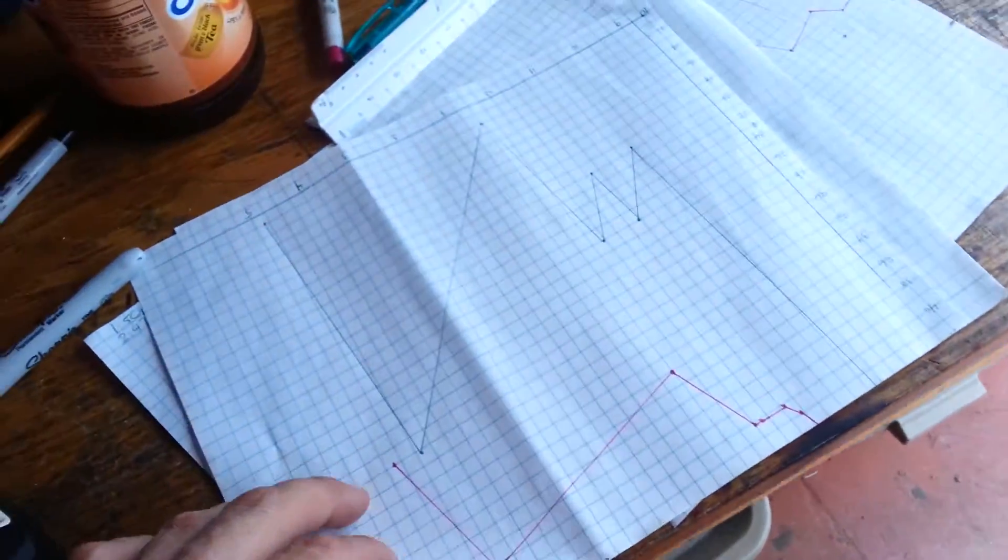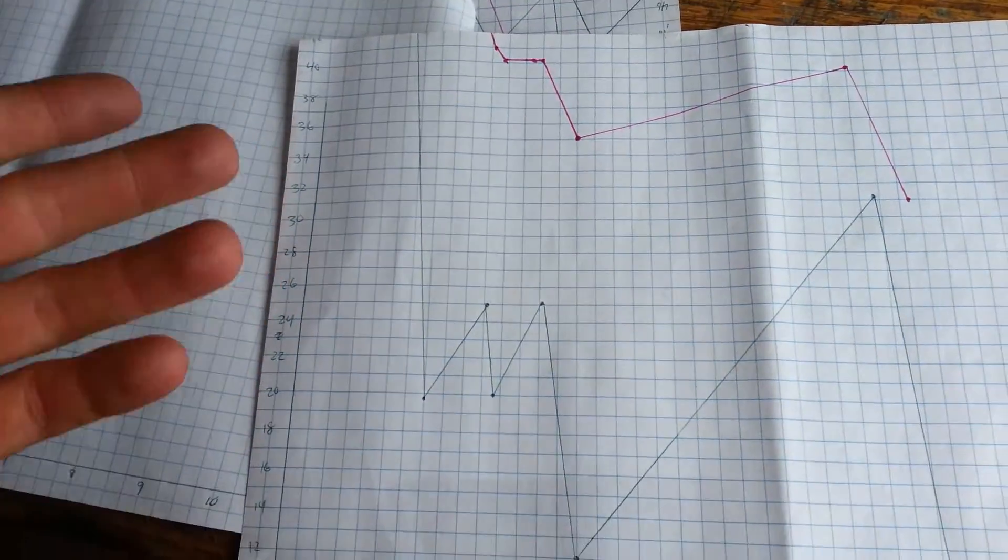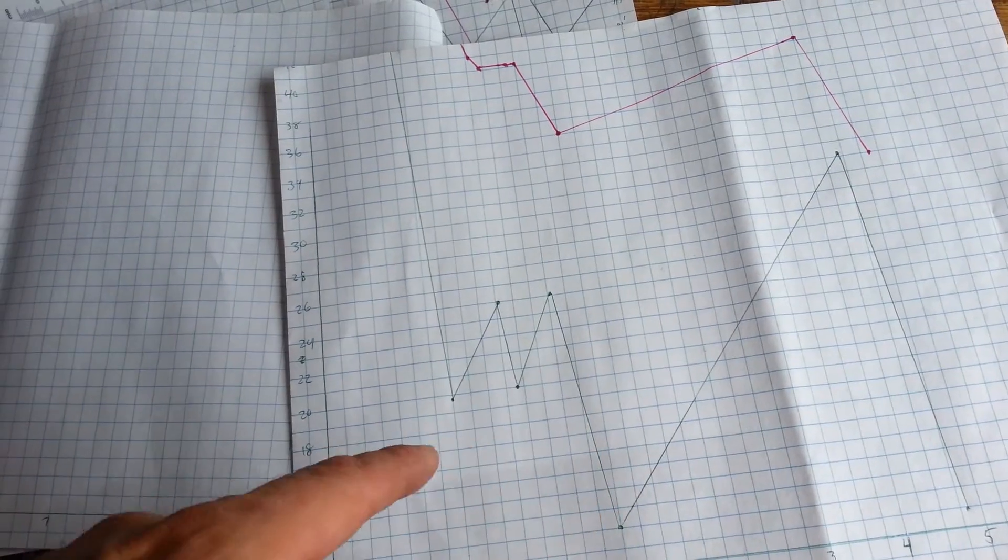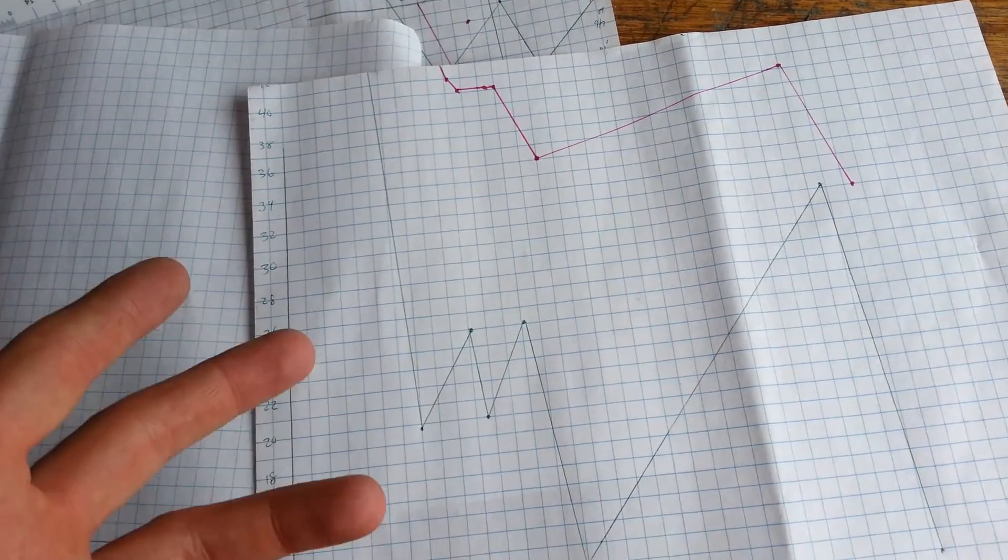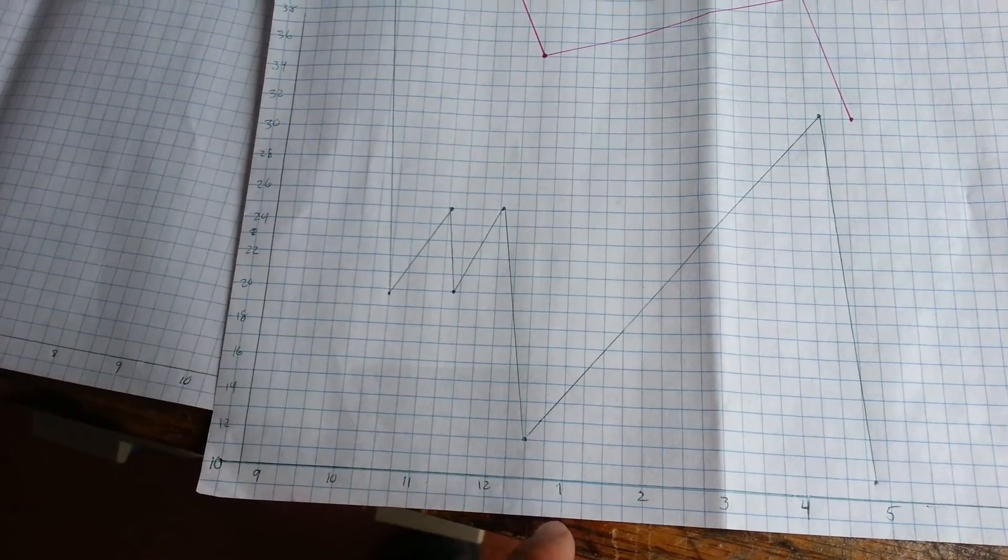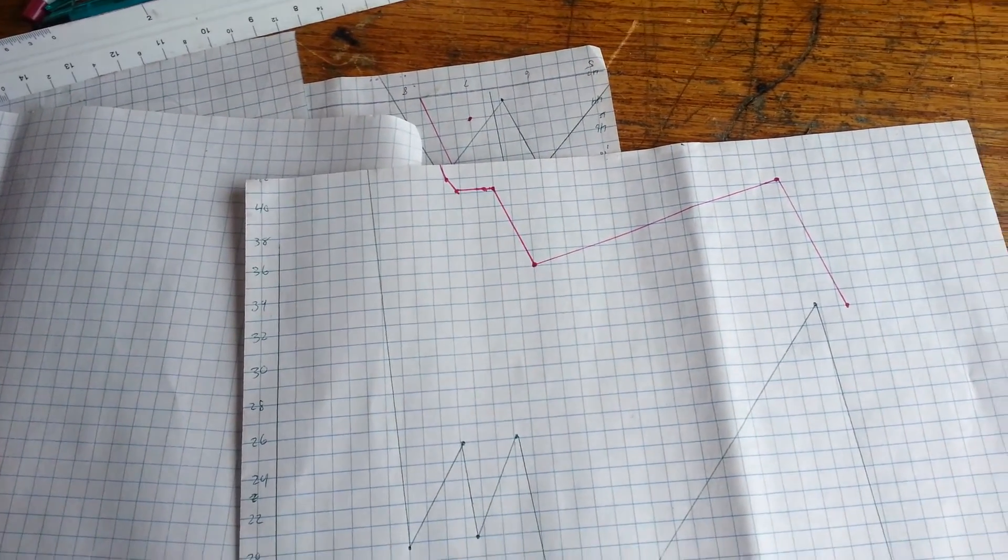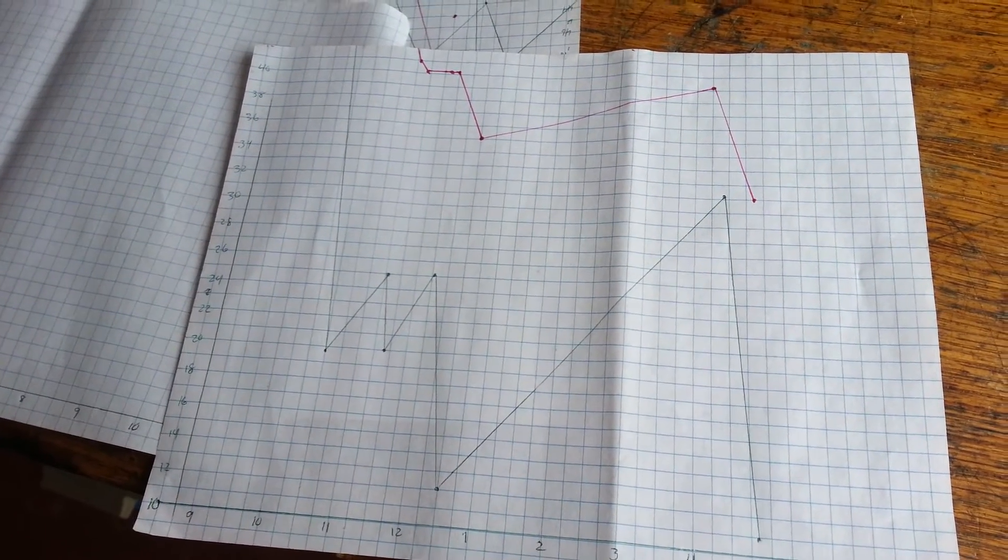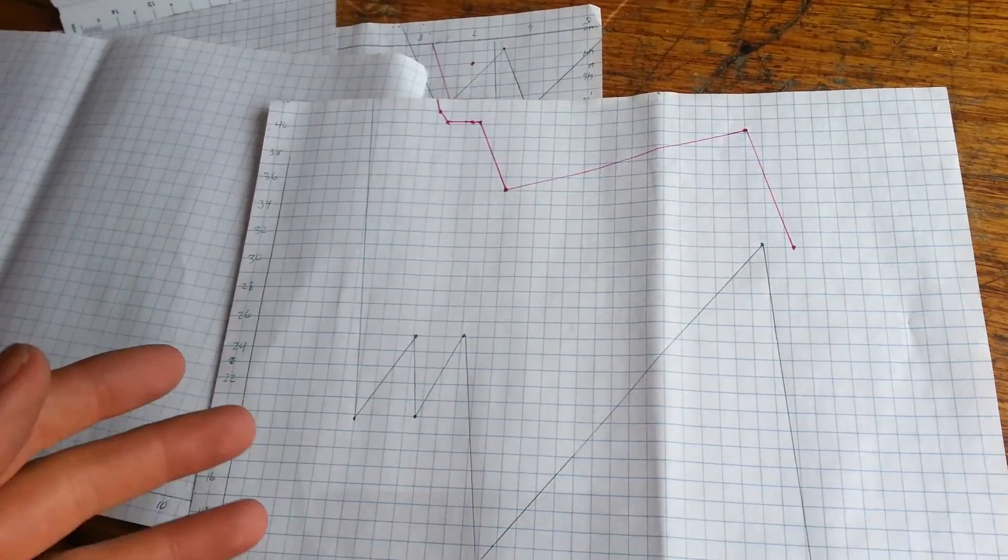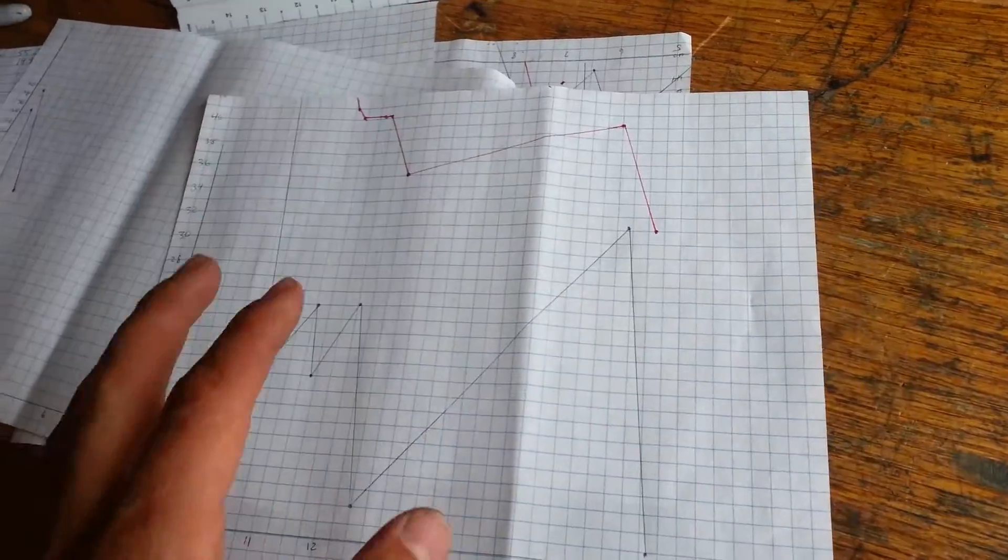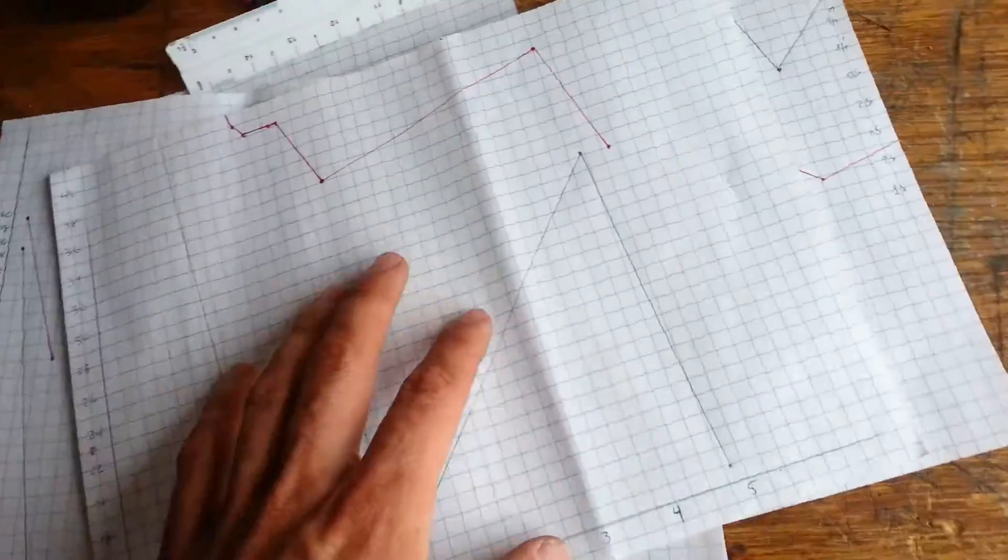I ran this thing most of the day yesterday. I kind of did some crude graphing here. The performance, that green line there is the compressor. Initially, I was cycling between 20 and 25 degrees Fahrenheit, and then I decided to switch to about 15 degrees Fahrenheit. At one point, I wasn't paying attention, I pulled it down to 12. You can see the pink line there. That's the cabinet temperature. I was getting about a holdover of something like three and a half hours. It would run for about a half an hour and off for three and a half hours, but I don't have enough information to really get a good idea of the characteristics of this box with this arrangement.